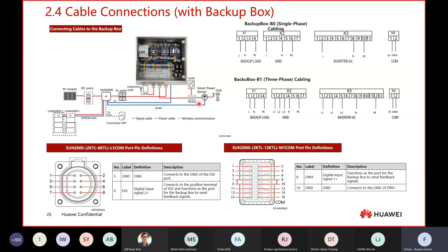Easy to understand. Okay, third is the short circuit plate. This one is for the short circuit, depending on which grid code you're using and how your electrical system is, maybe IT. For this backup box, the inverter has a separate alarm, normally an alarm ID. This alarm ID shows what the problem of the backup box is, and we have the solution there. You can follow the solution to eliminate the alarm.